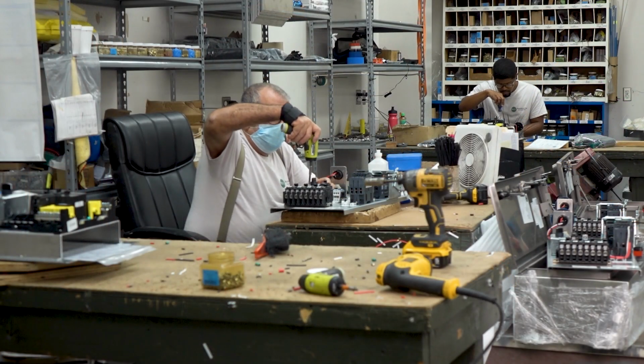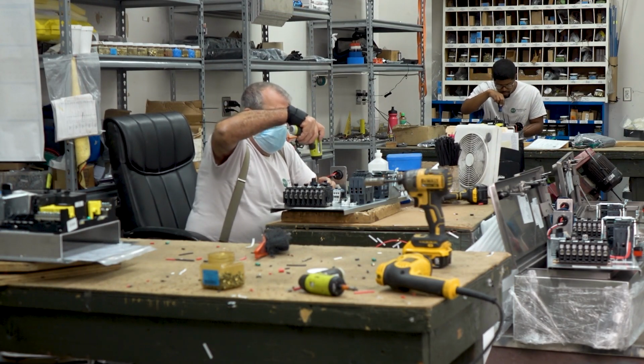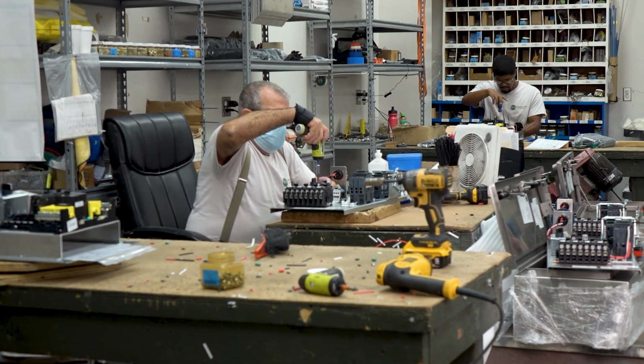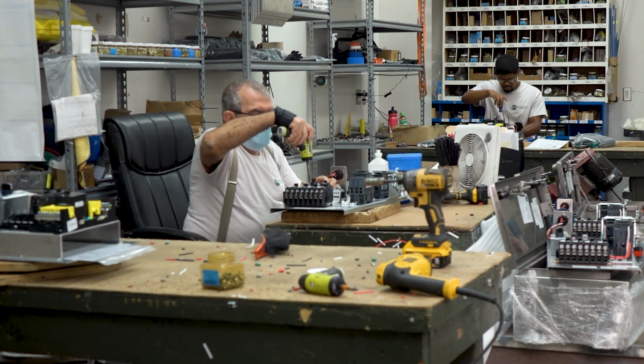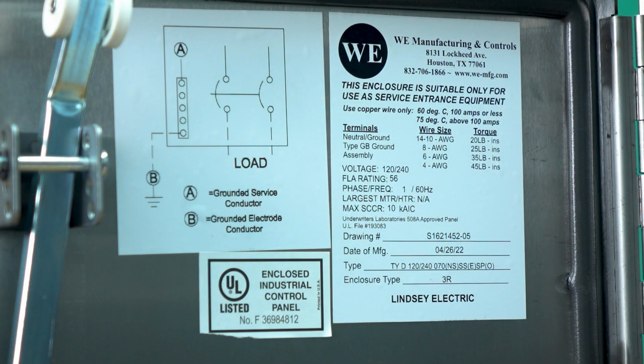The Type D service is required by the plans to be built only by a UL-listed industrial control panel shop. A label with the shop information must be attached to the inside of the door. This label should clearly show the name, location, and phone number of the shop, the UL file number of the 508 shop, the shop order or drawing number, the date of manufacture or assembly, and the line voltage.